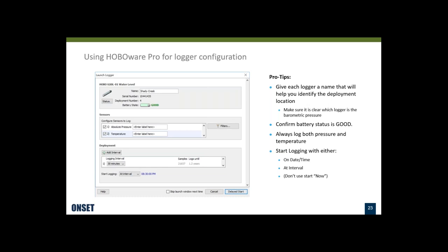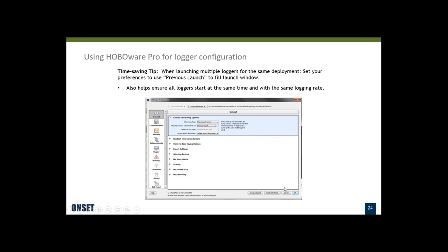We have an option for starting now, but typically you don't want to just start now because your data will be at a random time. If you're logging every five minutes, you want it to log at 10:00, 10:05, 10:10 — at nice even intervals, not starting at 10:02 and a half. It just makes it a lot easier to process and correlate the data if you use either 'at interval' or a date-time start. Once you've set your logger up, you click the key for delayed start. A time-saving tip: under HOBOware preferences, use the launch time savings option so the contents of the previous launch for that logger type fill the next launch window — this ensures all loggers start at the same time with the same logging interval.